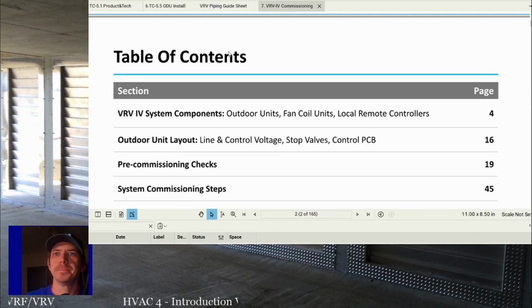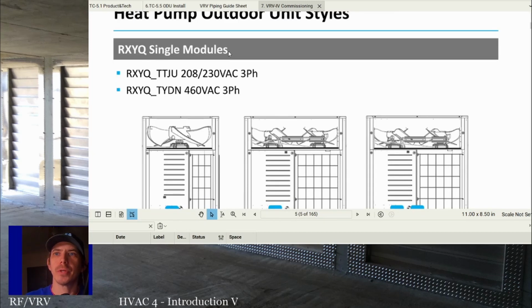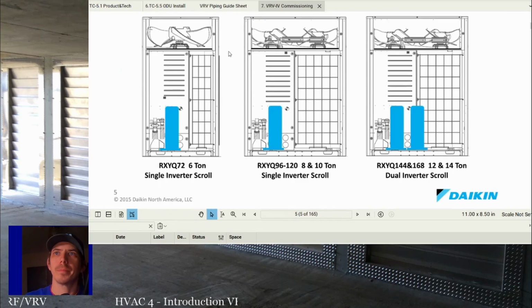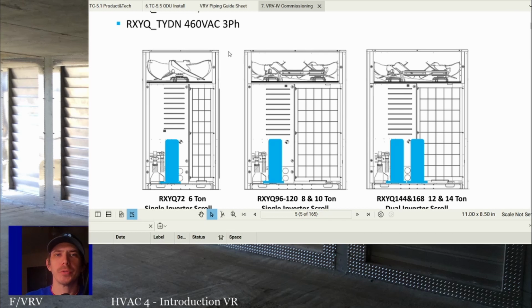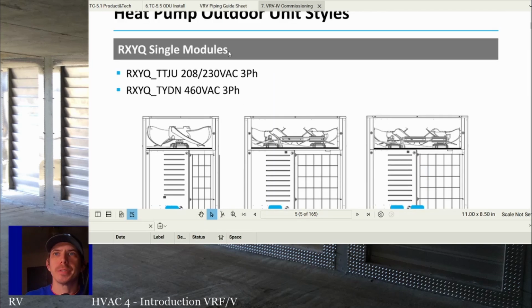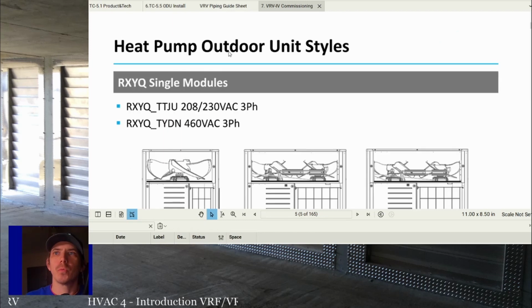So let's go through the individual components of a VRV system or VRF system, and let's talk about what they are. Most of these things should be relatively familiar from any AC or heat pump system, and you'll see that it looks a little more like mini splits than anything else. But it's basic stuff. So you've got outdoor units. Real quick, point number one, heat pump outdoor units. There's no straight AC VRF system. You have heat pumps and you have heat recovery. Most of what we're going to cover is heat recovery because it's more complicated than the heat pump. And if you understand the heat recovery, you'll understand the heat pump.